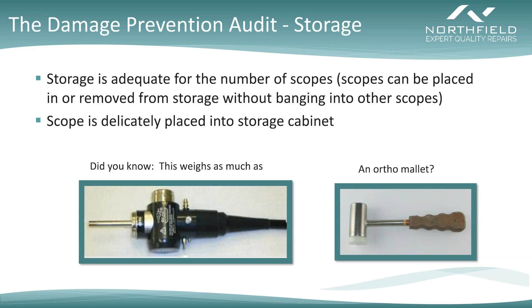And so if you bump into it, if you're putting it in too quickly, it's potentially slamming into those distal tips and doing crush damage. Depending upon what part hits the bending rubber area, it could be leading to punctures. And all of that is going to lead to some very expensive repairs. And I promise you the repairs will be more expensive than it would have cost to just make sure you have an adequate amount of storage in the first place. So look at your storage, watch people load scopes in and take scopes out. Do they bump into other scopes? Do the light guide connectors go swinging around? Is it banging into other scopes? If so, you might need more storage.